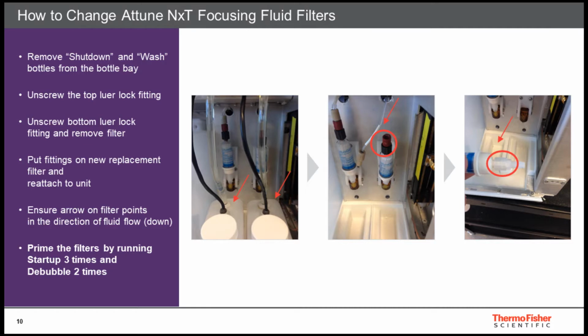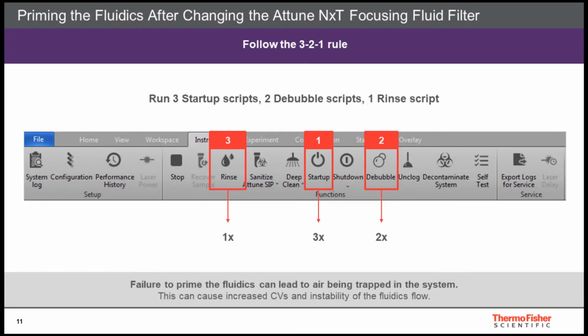Secure the top and the bottom luer locks and ensure that they are tight as to not leak. Add the retention straps back on and prime the lines. To prime lines in the Attune NxT Flow Cytometer, please remember a simple rule of 3-2-1. Run 3 startups, followed by 2 debubbles and 1 rinse to purge all the air out of the system.